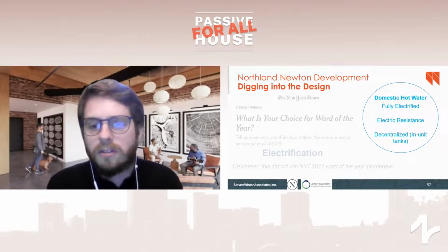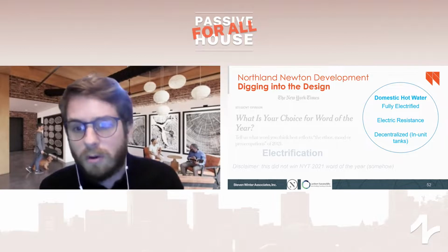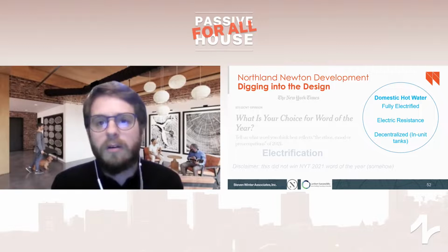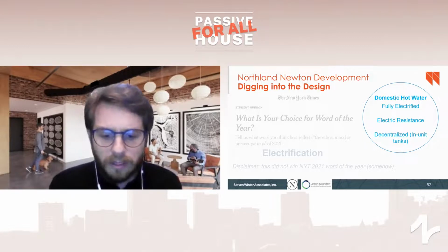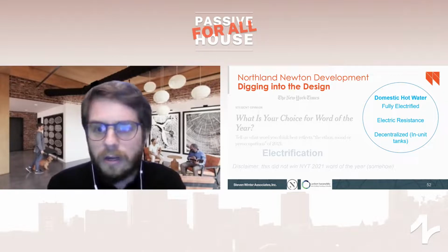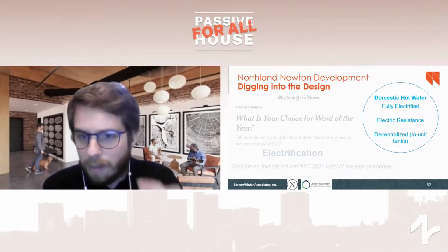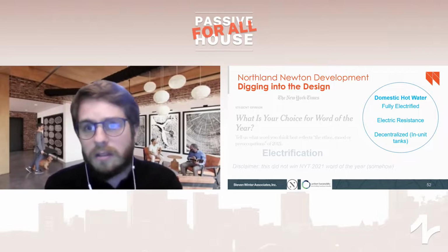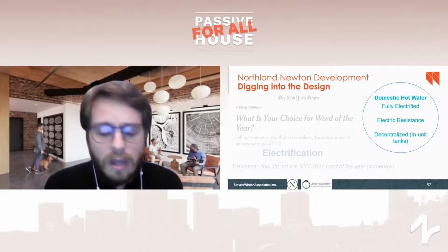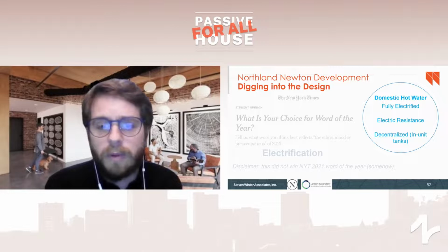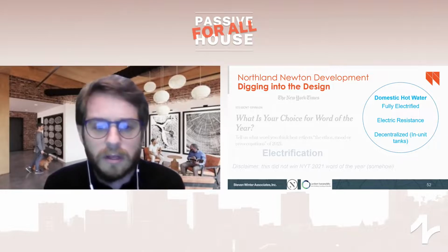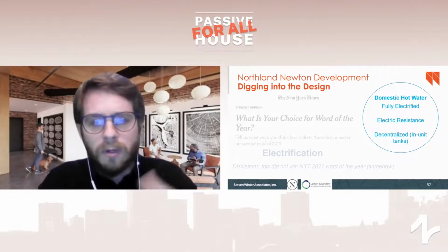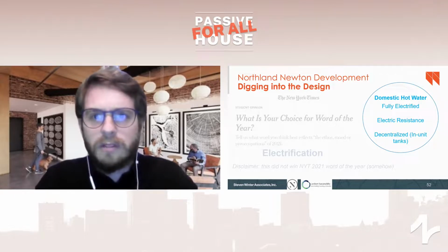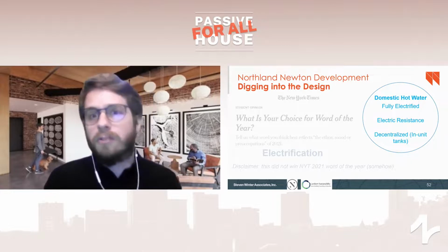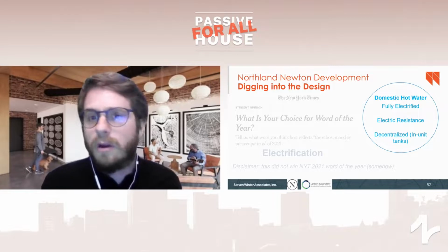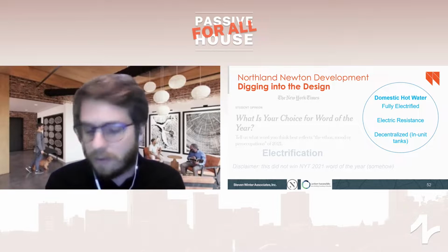And what we found is on a lot of projects, even where they are installed properly, complaints have caused owners or building operators to turn them into electric resistance mode year round. So what we looked at was, hey, we don't feel confident that we can really deliver a decentralized in-unit approach with heat pump water heaters in a way that we felt confident would actually be operated that way. So we looked at electric resistance, insulated tanks as the option, and really one thing that's nice about the primary energy renewable criteria for the passive house designers in the crowd is that it really is beneficial for all electric buildings, and you can go to electric resistance tanks. You can go to electric resistance tanks in unit for domestic hot water and still meet the passive house primary energy thresholds. And that was the case for this project.